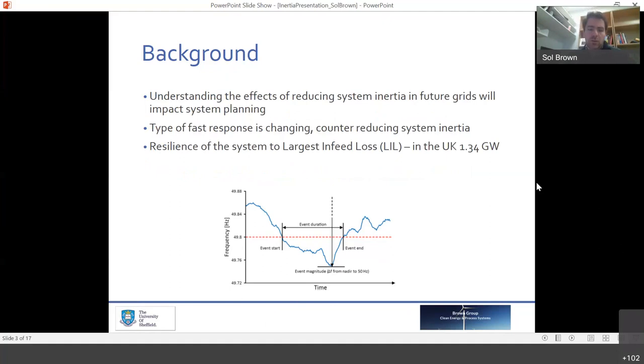Right. So we really need to understand the effects of this reduction in inertia so that we can plan our system going forward, both the types of fast acting responsive generation that we have, that might be storage or that might be reactive or responsive dispatchable power in the form of gas turbines or whatever we look for in the future, and also resilience to largest loss events. So in the UK, that's currently about 1.34 gigawatts. That would be one power station, which is Drax in Yorkshire. Going forward, that's likely to change.